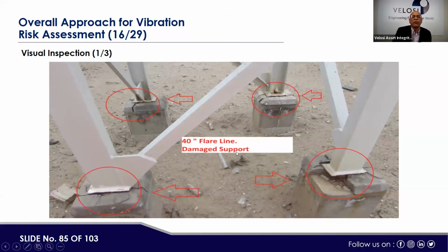See, a flare normally has very high velocity in operation because it operates maybe once in 3 years, 2 years, whenever there is an upset at the plant. And due to that upset, the flow load could be very high when full flow is coming to the flare side of the gases, and it may cause high vibration. And we have seen at least one case where a flare line fell just after pre-commissioning of the plant. So the flare sizing and associated supports are required to be addressed properly.